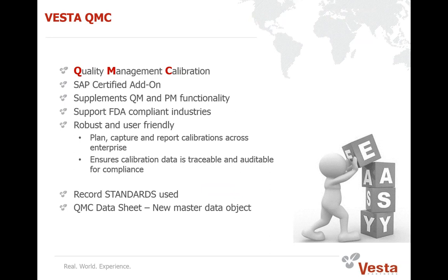Secondly, during the capturing of your calibration information in the inspection lot, we have some additional information. We can record lab standards that were used at this point. And then thirdly, on the reporting side, we have a few reports available, and we also have the ability to print a calibration certificate for you based on your inspection lot results.